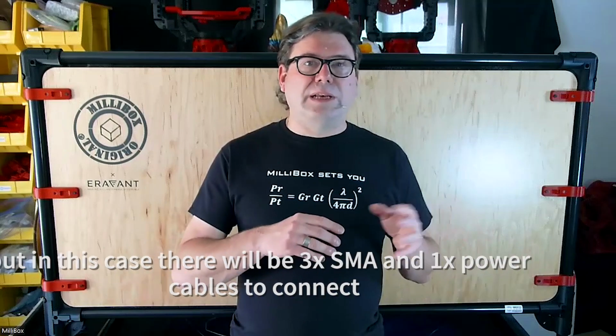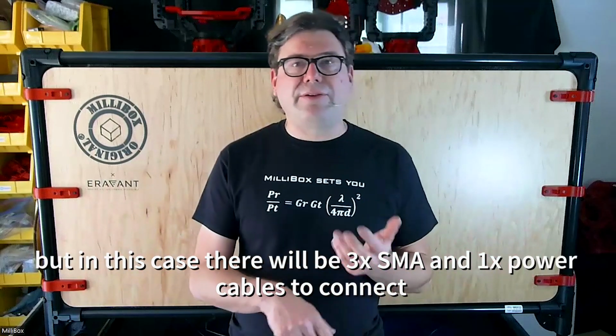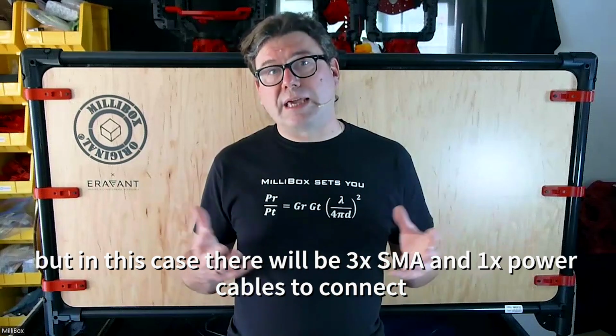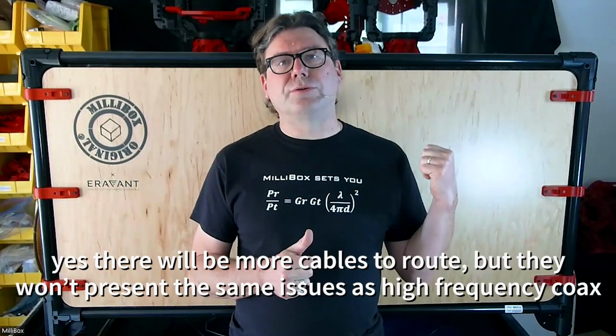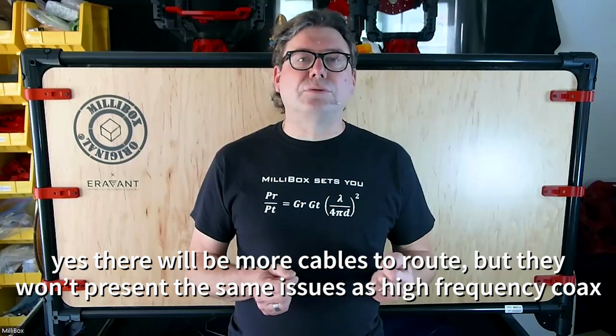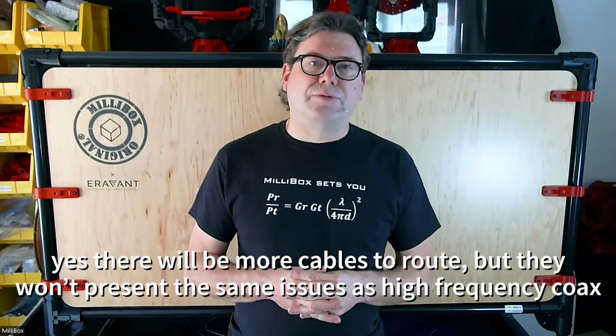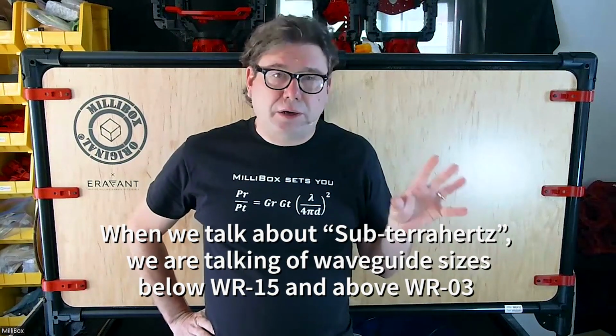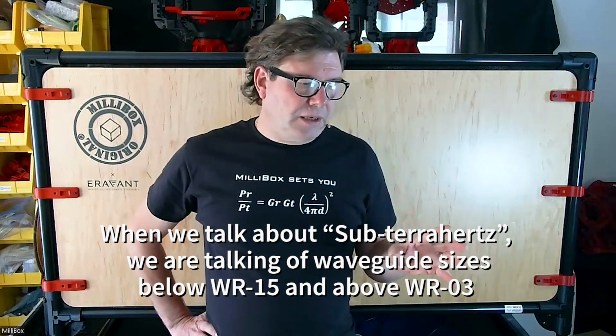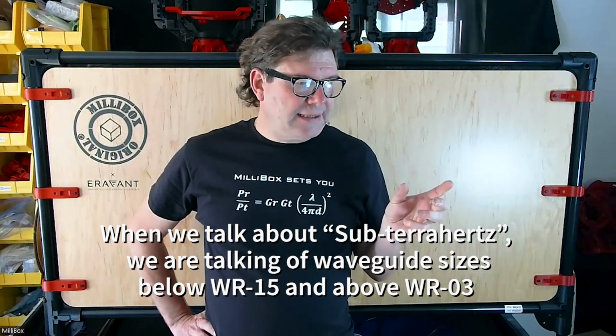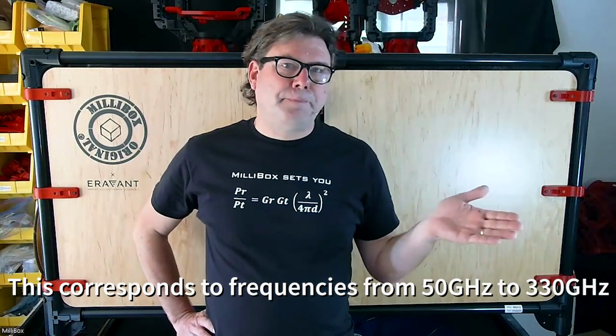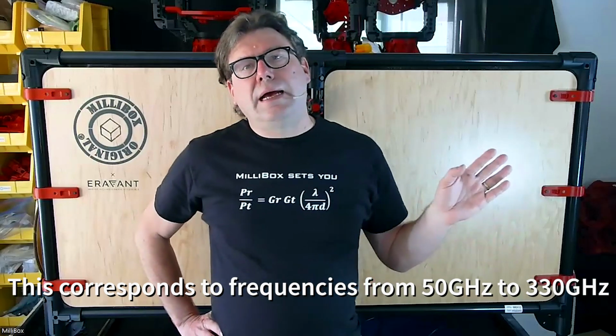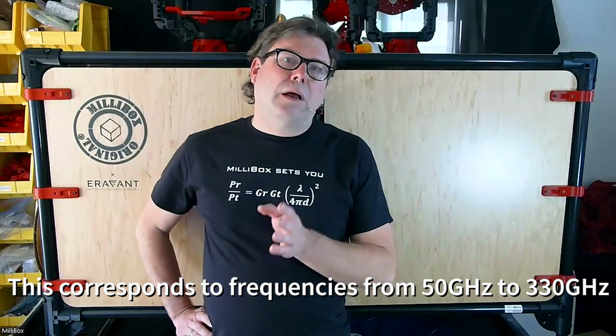But in that case, we'll have more cables. We'll have LO, measurement, RF, ref, and power supply. So we'll have more cables to run through, and we are going to go through that. But on the other hand, we don't have to run such high frequencies on a flexible coax. When we are talking about sub-THz, what we mean is, if we're talking about waveguide standard sizes, we're talking from WR15. We started at 50 gigahertz, and we go to WR3 at 330 gigahertz. Basically, you have WR15, WR12, WR10, WR8, WR6, WR5, and WR3.